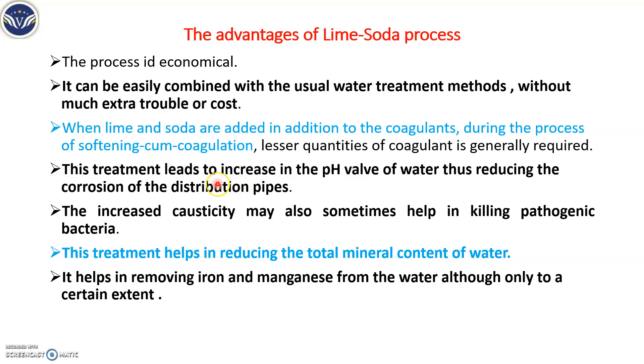When you add lime soda in the treatment units, it increases the pH value. By increasing the pH value, the corrosion of pipes which takes place due to acidic conditions will be quite reduced. Another advantage is it will help in killing bacteria, as there is a rise in pH — the rise in alkalinity means pathogenic bacteria cannot bear it.